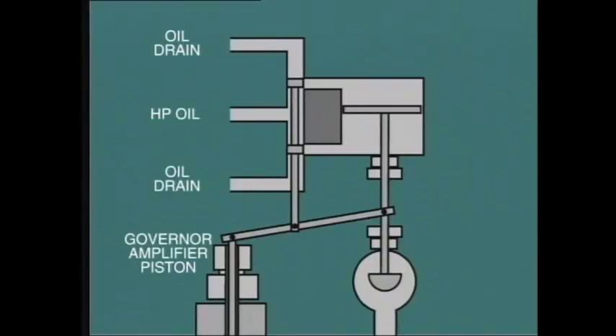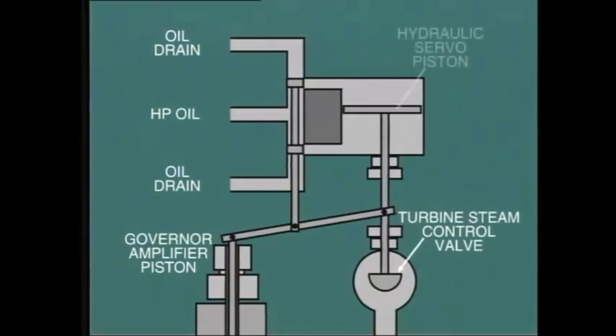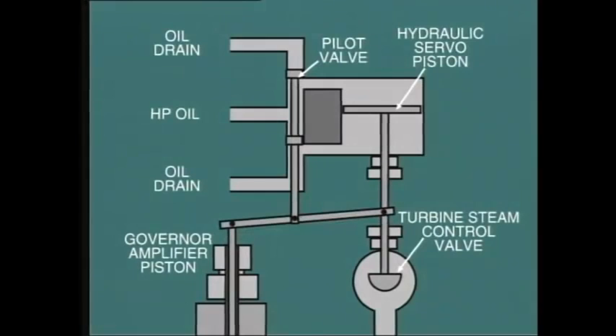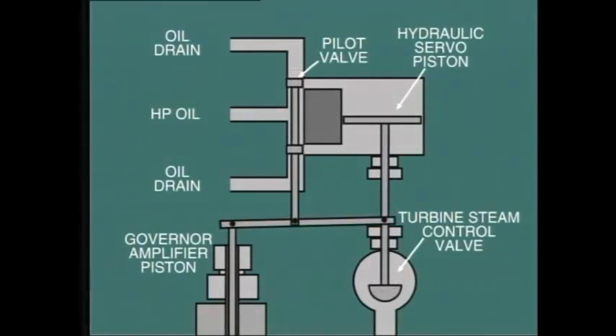In this simplified example shown here, the turbine steam control valve is adjusted by the position of the hydraulic servo piston. This large system is controlled by the small pilot valve here. Now, suppose the governor control system lifts the operating lever slightly. As we can see, this will now allow high-pressure oil to enter the servo cylinder above the piston. At the same time, it will allow oil below the piston to pass to the oil drain. In response to this, the piston will be forced downwards, partially closing the control valve. But look, this movement downward also moves the operating lever, and this moves the pilot valve downward, so closing off the servo cylinder, which is now in a new position.